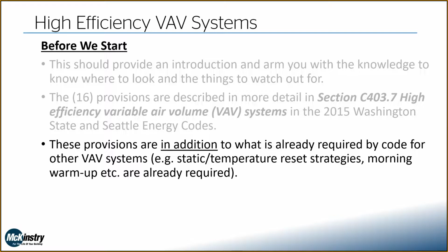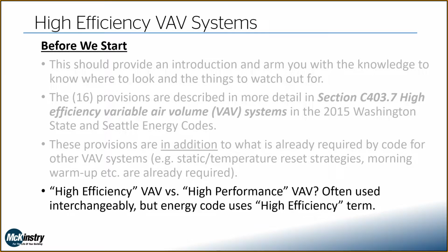So the code already says you need to do static and temperature reset strategies, morning warm-up. So the provisions to meet high efficiency VAV don't necessarily talk about those things, because those would be required for any VAV system, not just high efficiency VAV. And in terms of the terms that are used, high efficiency VAV versus high performance VAV, I see these terms used interchangeably. I've always taken them to mean the same thing, but in terms of what the code says, they use high efficiency VAV as their term.